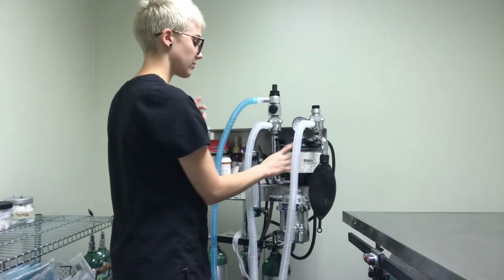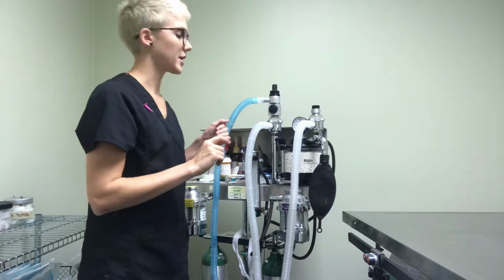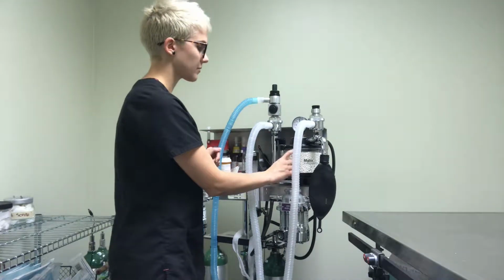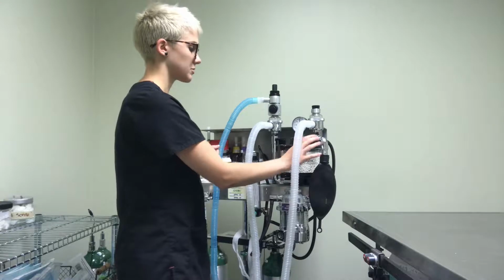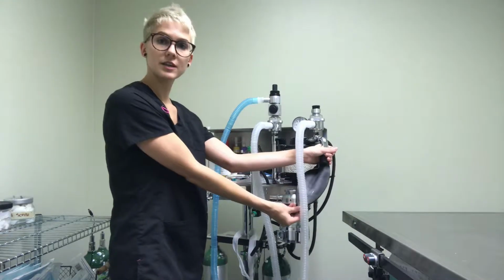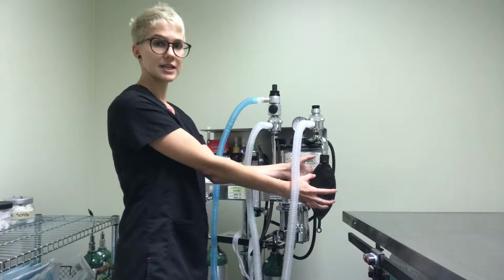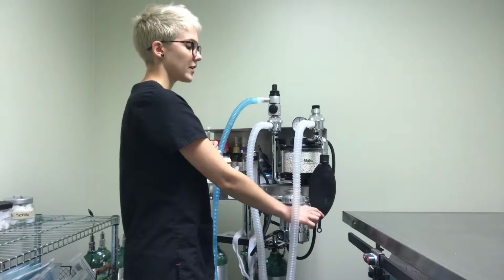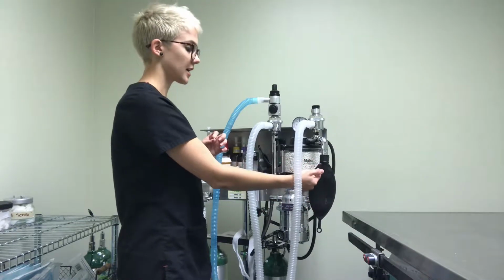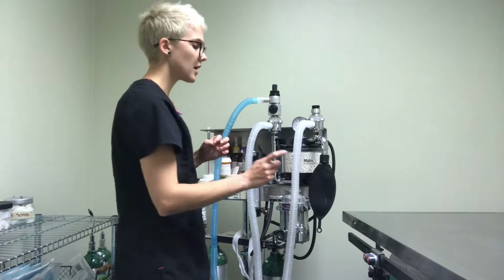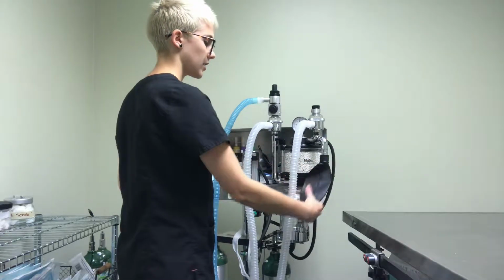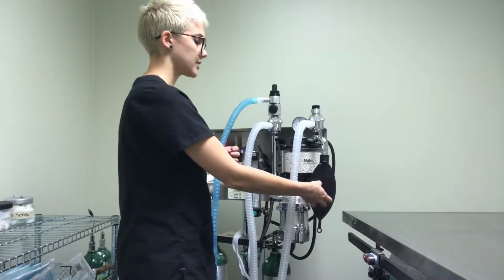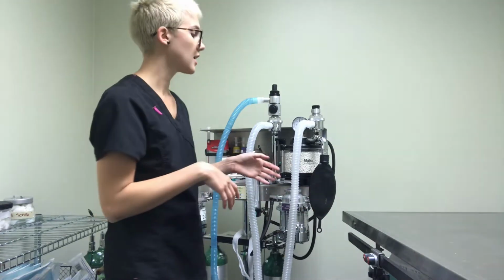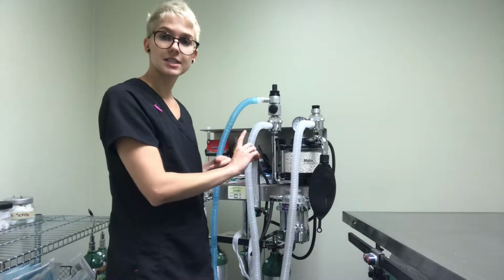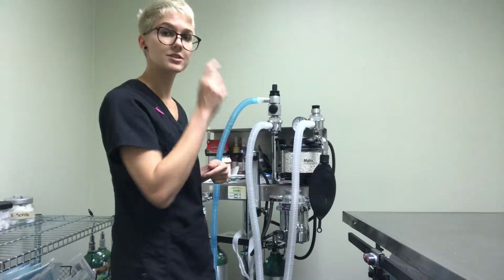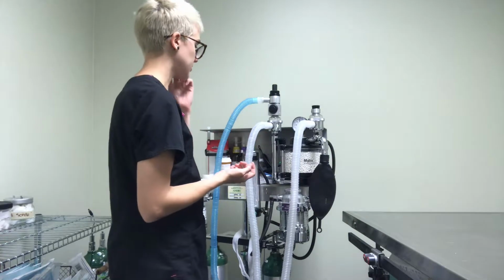And then once it goes through there, when we're using a reservoir bag or a rebreathing bag, it exits from the CO2 absorber and into the bag right here. So this inflates. This is full of waste anesthetic gas, and also oxygen. So this is a rebreather, so it's more efficient for larger patients to reuse the waste anesthetic gas, so it gets recycled into the system and gets fed back to the patient.